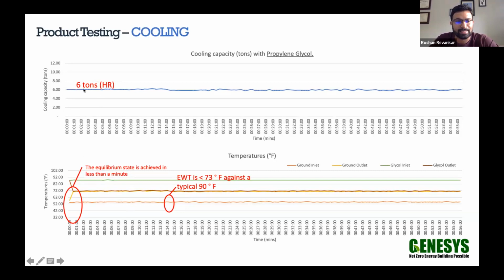Like I said, 6 tons nominal capacity for 56-degree groundwater temperature. In cooling mode, it enters at 56 degrees and leaves the heat exchanger at 72 degrees, a little less than 70 degrees here in this case. And on the closed loop side, this is what your heat pump is going to see. It supplies temperatures close to 90 coming from the heat pump, going into the CLAD, and it goes back to the heat pump at 73 degrees.